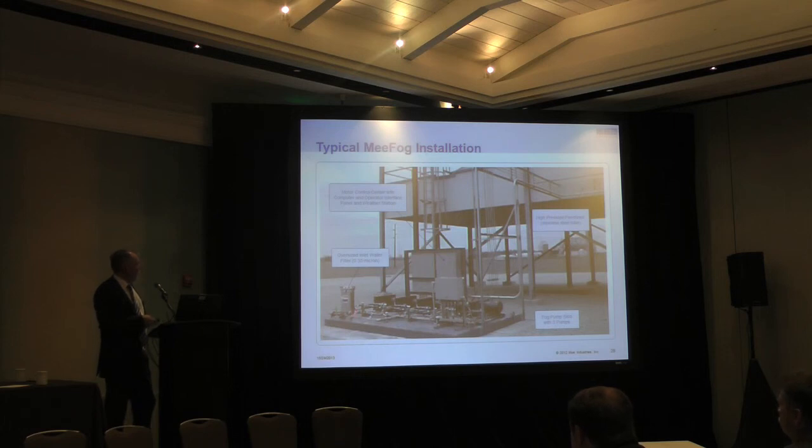That's a filter on the skid. We always have a submicron filter on the skid. Some water treatment systems, if you have twin bed deionization instead of RO, for example, and you're pumping river water, there can be colloidal silica in the water that's not removed by the purification system. It's not dissolved, it's colloidal particles, but it can actually damage the fog nozzle, so we always filter on the skid to make sure that that doesn't occur.